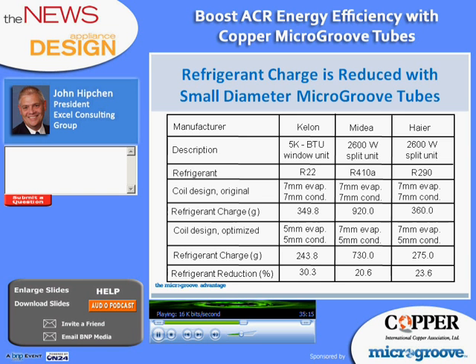This time, the OEMs that contributed the data approved the release of their names. So we see in this chart 3 different manufacturers. We see 2 different types of systems, window units and split type systems, and 3 different refrigerants. If you don't recognize R290, that's the name for propane.